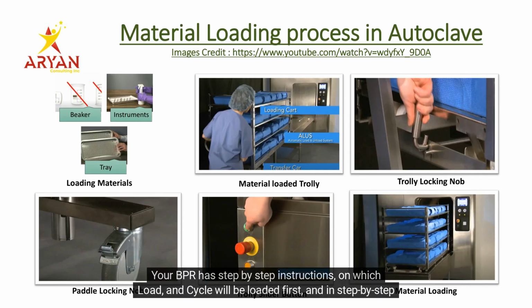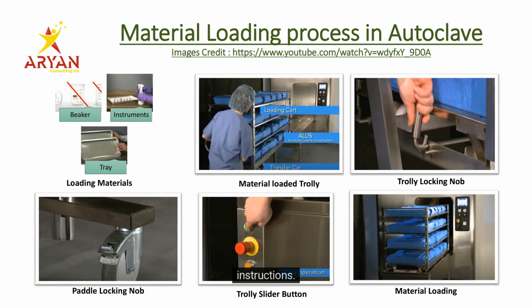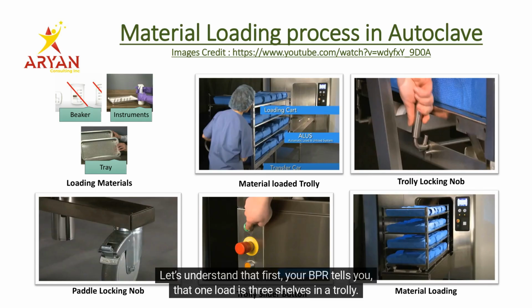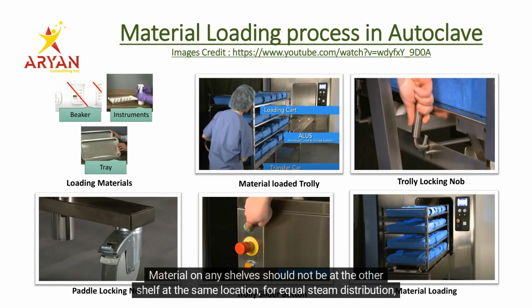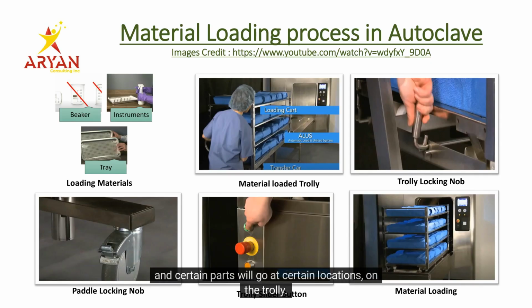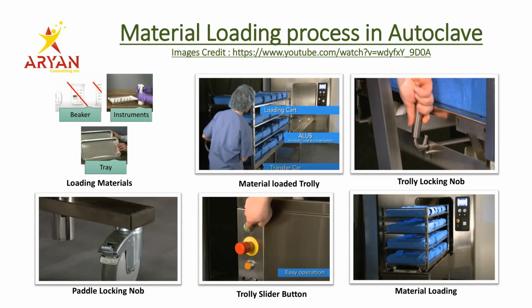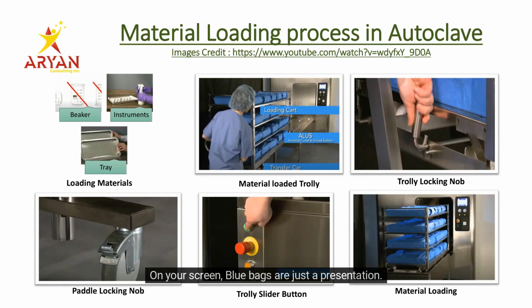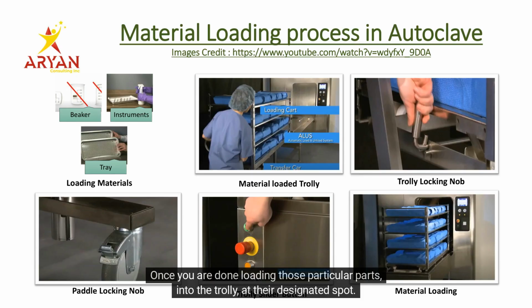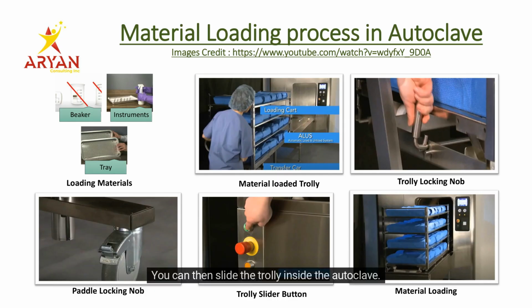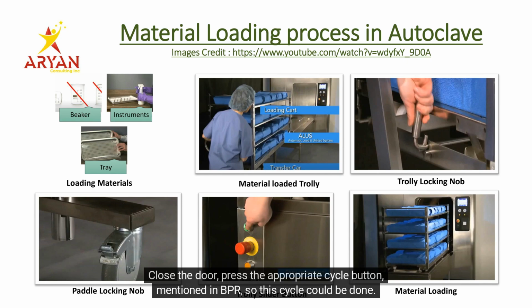Your BPR has step-by-step instructions on which load and cycle will be loaded first. Let's understand that first. Your BPR tells you that one load is 3 shelves in a trolley. Material on any shelf should not be at the same location as on another shelf, for equal steam distribution, and certain parts will go at certain locations on the trolley. On your screen, the blue bags are just a presentation. Once you are done loading those particular parts into the trolley at their designated spot, you can slide the trolley inside the autoclave, close the door, and press the appropriate cycle button mentioned in the BPR so this cycle can be done.